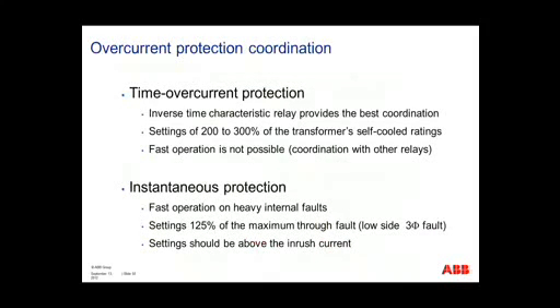I'm not sure of the question. Location of the three-phase faults. Okay, the worst case is close in, so just outside the transformer bay is your worst case. That's where you need to do your study. Okay. The worst case is just external to the relay. A close-in, external, low-side three-phase fault will be your worst case.